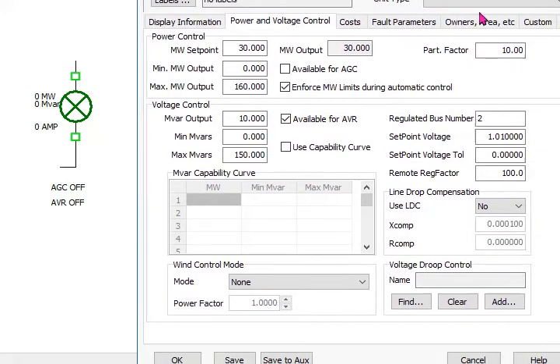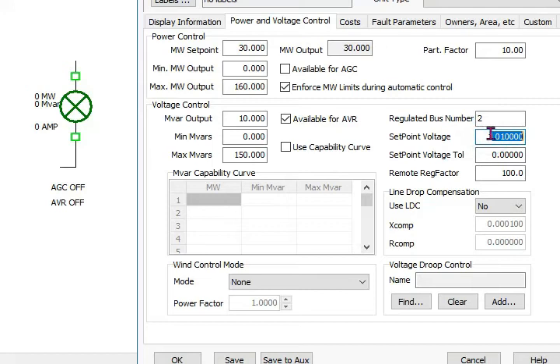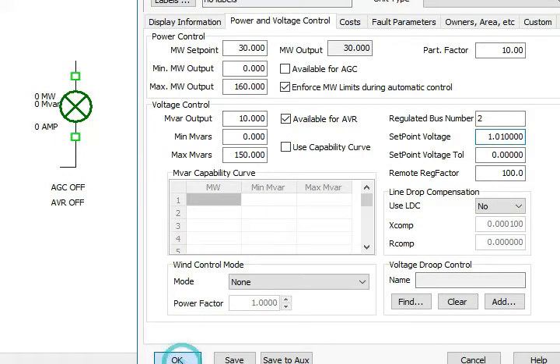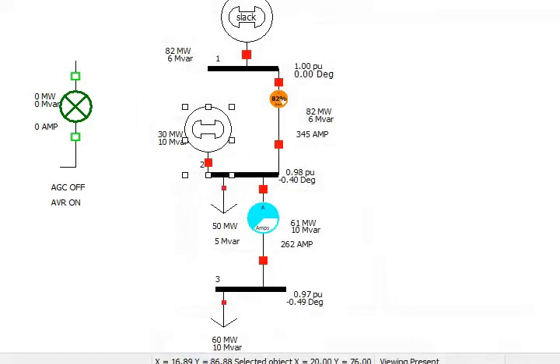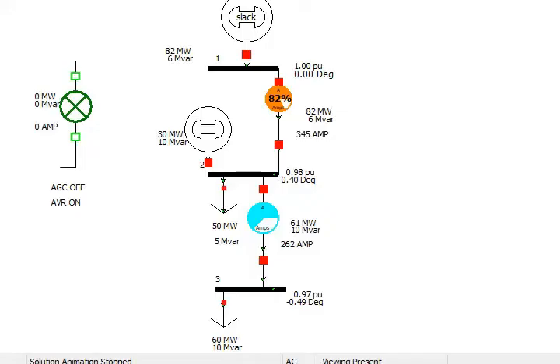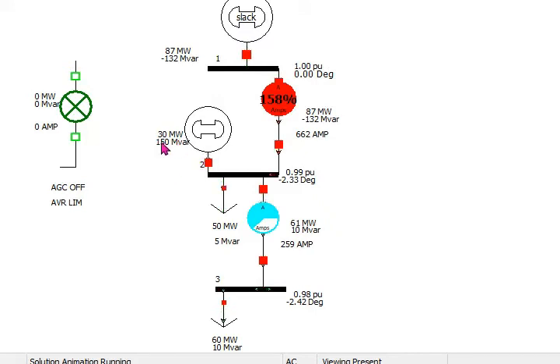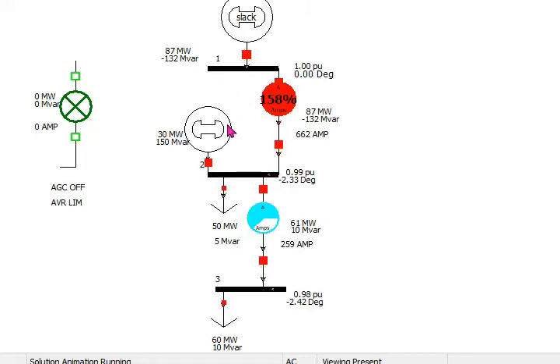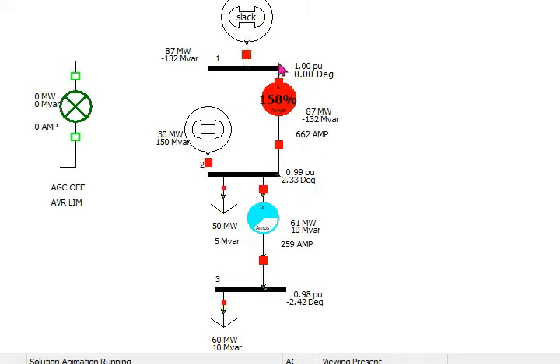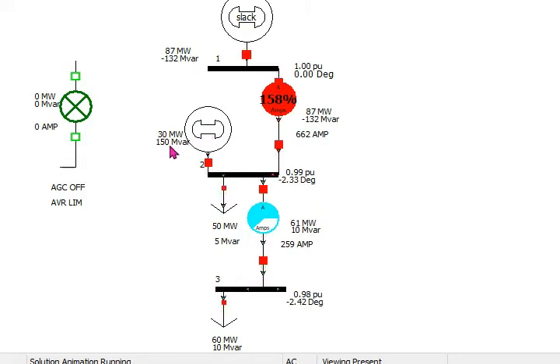This generator will try to maintain 1.01 per unit at this bus. The DG will try to adjust the reactive power in such a way that to maintain the 1.01. You can see that the first transmission line is overloaded to 158 percent. The reason is that it started back flowing the reactive power through this generator. Because this generator could not maintain the 1.01 voltage, instead the voltage at this bus is 0.99.